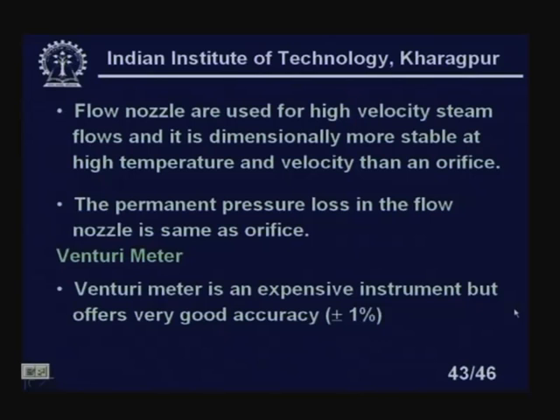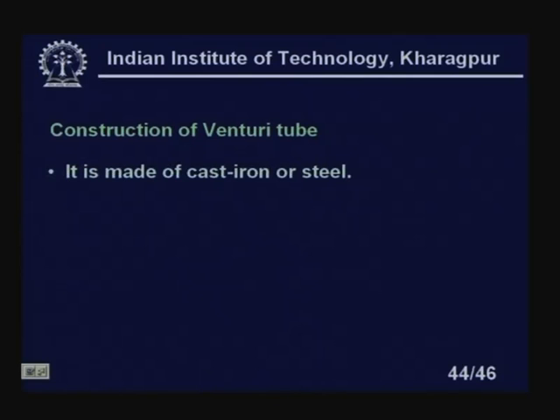The venturi meter is an expensive instrument but offers very good accuracy — plus or minus 1 percent. It has the lowest permanent pressure loss. Looking at its construction: it is made of cast iron or steel, and large venturi tubes can be made of concrete. The throat portion of the venturi is sometimes made of bronze for easy replaceability. The venturi has an upstream section and a converging section down to the throat, where a tap is placed.